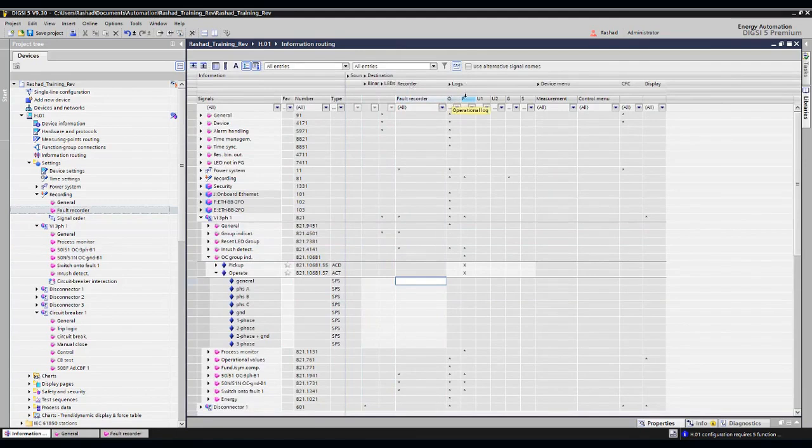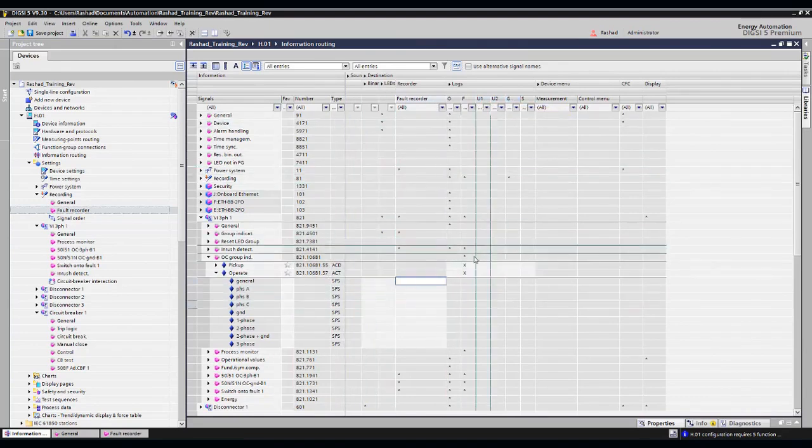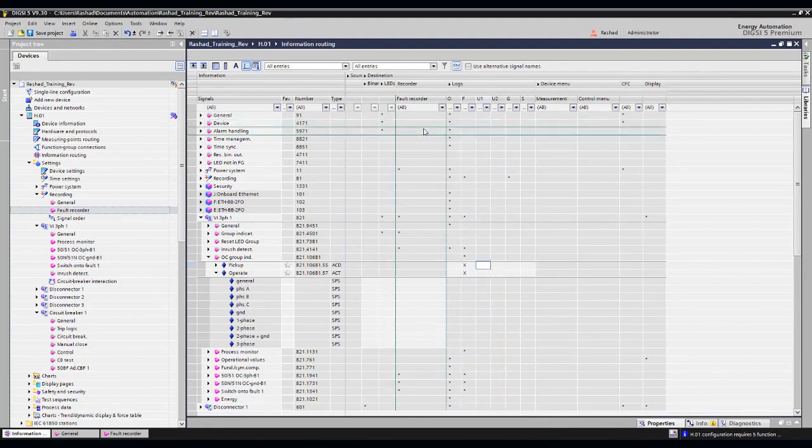Inside these logs, you have something called the operational log, something called the fault log, and the user-defined log. Another user-defined log is the ground log, and so on. So here you can simply add a set of signals in the user-defined log, and then through the relay screen, you can access these logs and see the things you programmed. When a fault occurs, you can see what events happened and what you instructed to be recorded here.